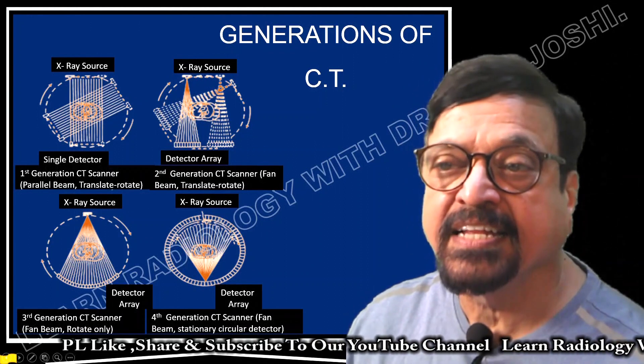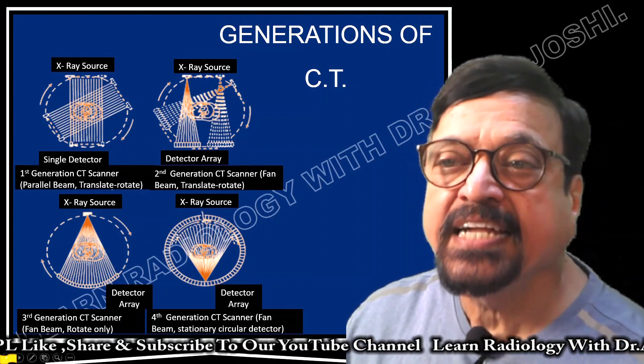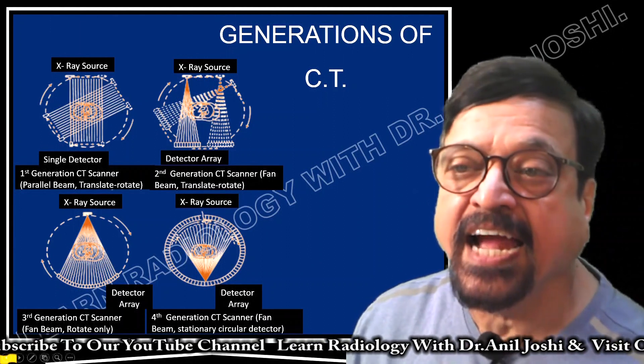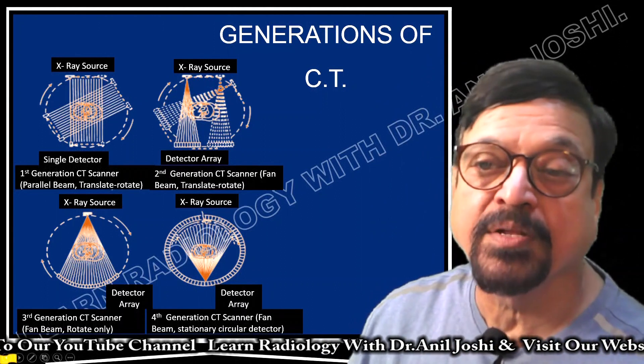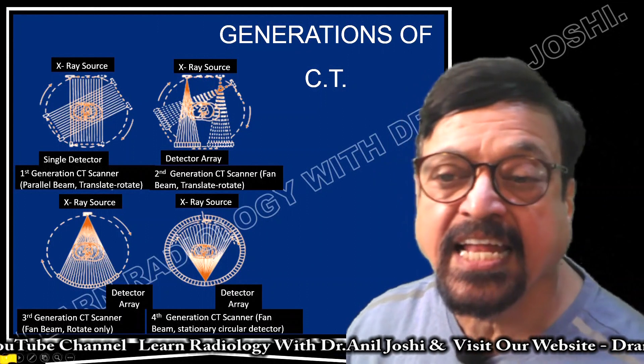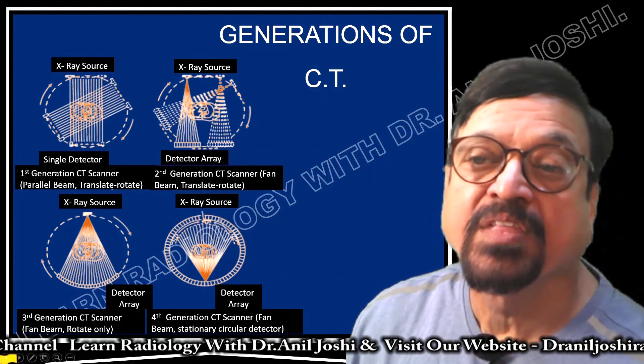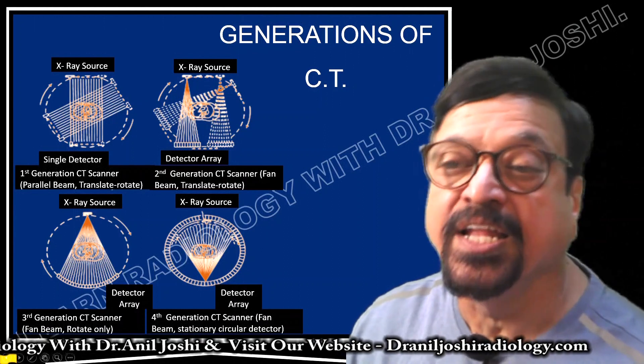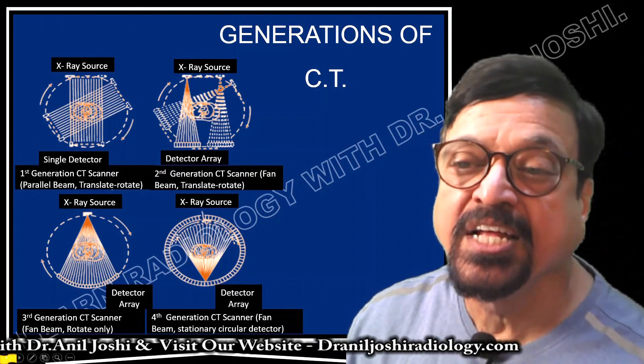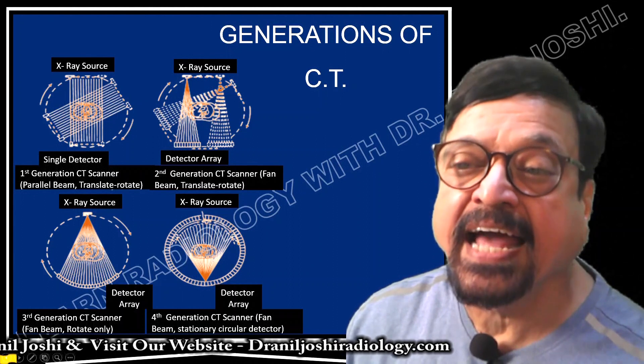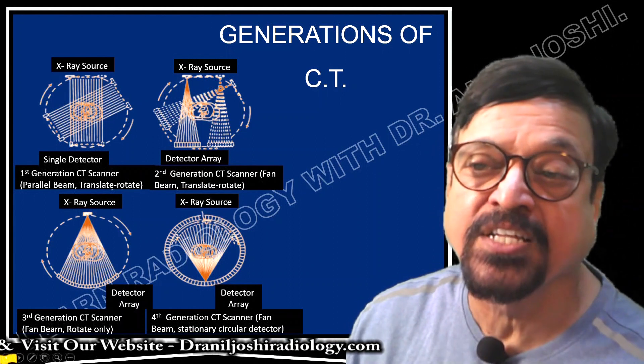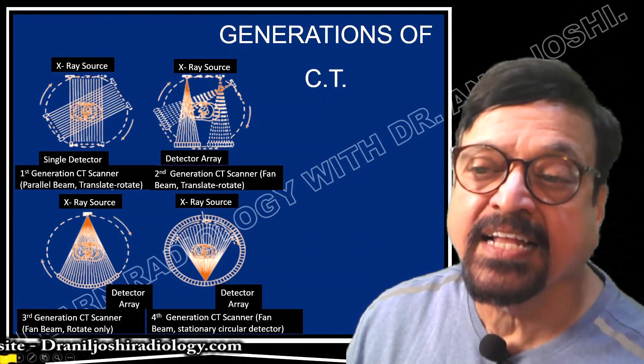In the second generation CT scanner there is a fan beam shape, and it is called translate-rotate. The tube is rotating and the detectors are also rotating, as you can see in the diagram. The third generation made a major revolution — it has a fan-shaped beam and is rotate-only. You can see the tube at one end and detectors at the other. This greatly changed CT machine speed and resolution. The fourth generation introduced detectors in an array along 360 degrees, with a fan beam and stationary detectors.